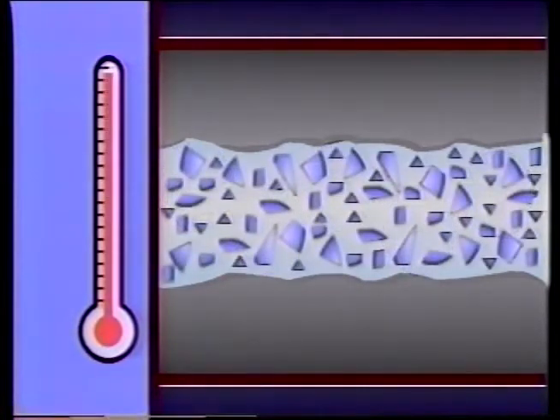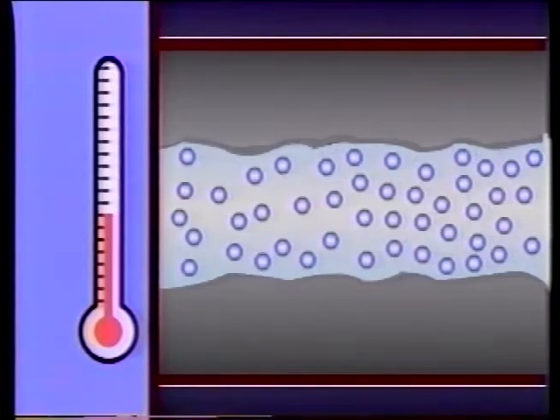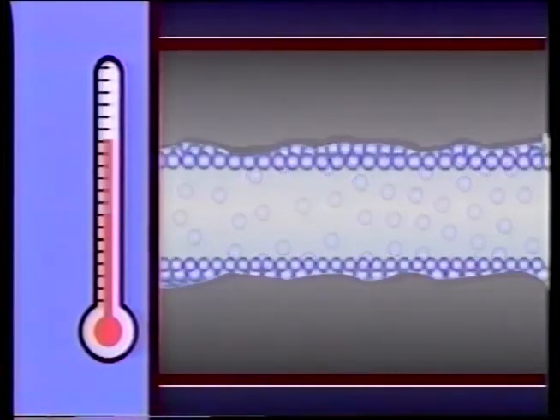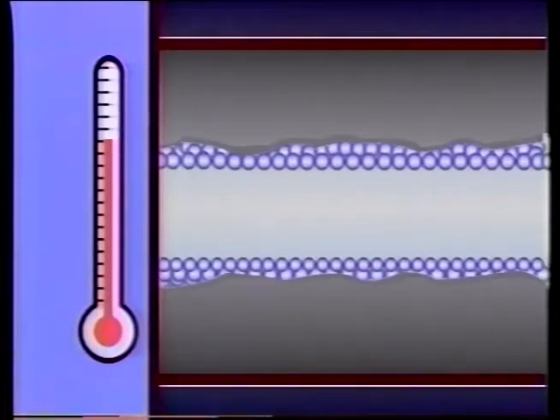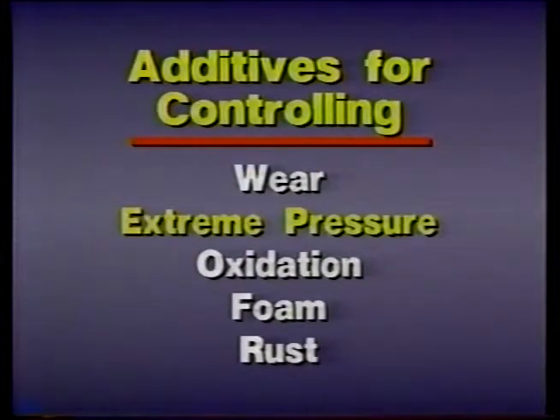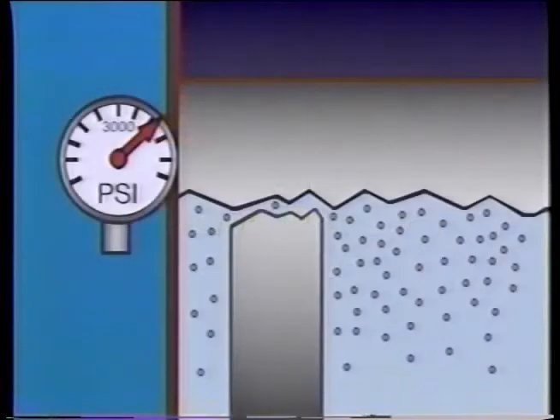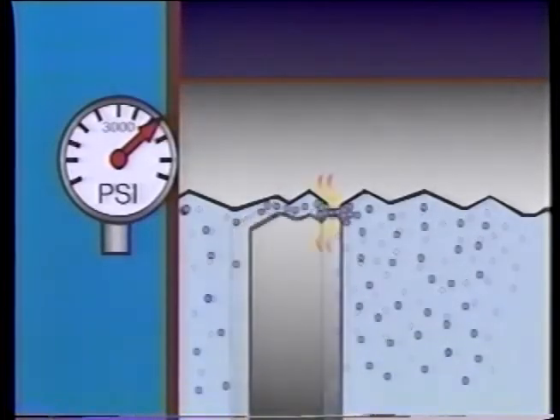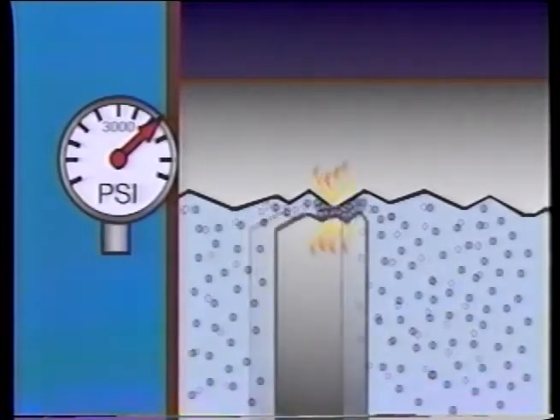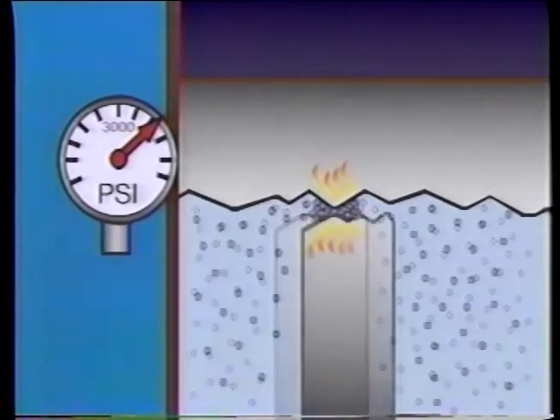To overcome this limitation, another type of anti-wear additive actually bonds with the metal as friction heats up the surfaces. The bonded molecules smooth out the surfaces and reduce wear. There are also additives made for systems that operate at extreme pressures, typically above 3,000 pounds per square inch. When systems operate at such high pressures, any surfaces which actually touch attempt to weld together. However, the high heat at these points activates the additive in the oil and keeps the surfaces apart.